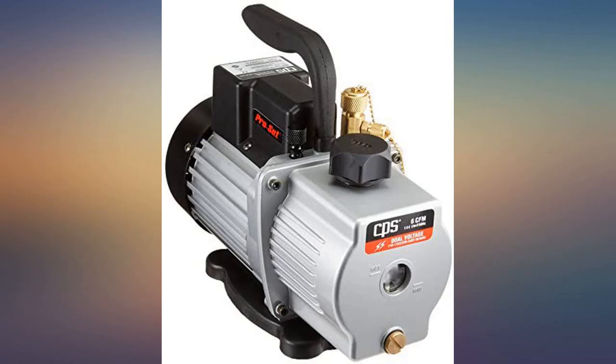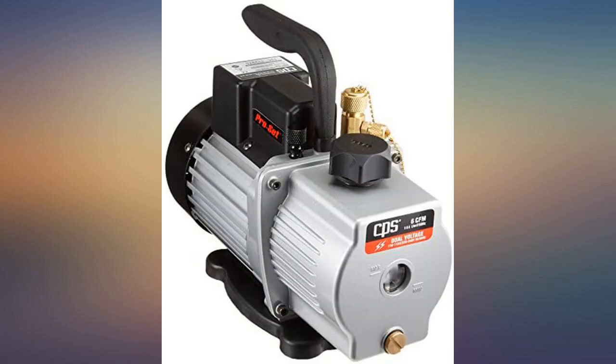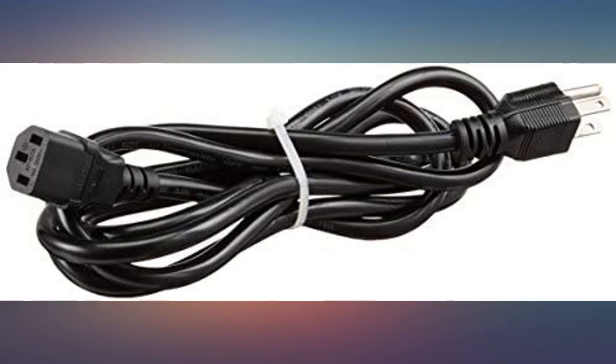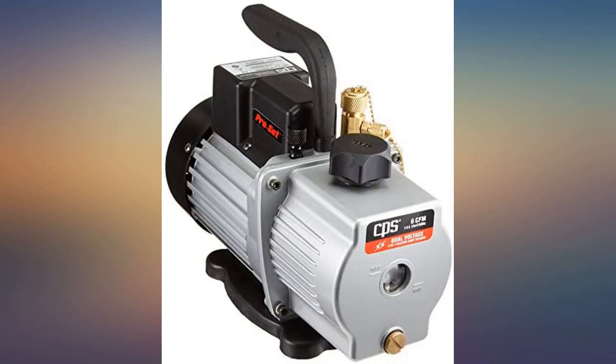Very solid pump so far. I didn't purchase from Amazon because the AC supply house I bought it from threw in a C13 corded plug straight to the pump, which comes in handy when using the 230-volt feature. I also have the CPS micron gauge. In some residential installs this pump pulls down to 200 microns in 10 to 15 minutes.